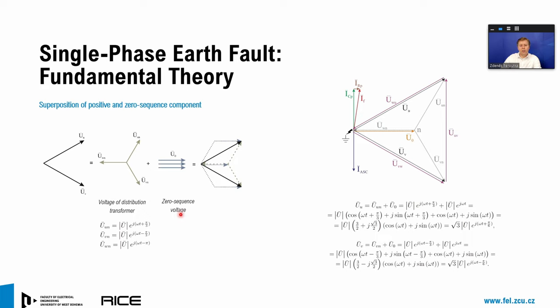When the earth fault occurs, the voltage vector diagram changes: the healthy phase-to-ground voltages become the line-to-line voltages, and we can decompose the final voltage vector diagram into the positive sequence component and the zero sequence component, to which we will pay the main attention today. That's what we are trying to work with when we would like to compensate the earth fault.